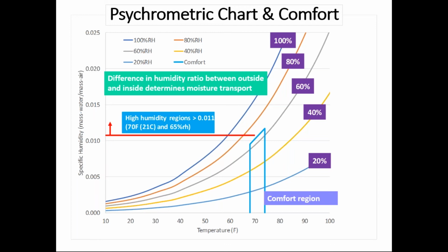Now, marked on this, roughly from about 68 degrees to about 74, 76 degrees is where most people feel comfortable, and over a fairly broad humidity range, up to about 65% relative humidity, which would be 0.01 to 0.011 humidity ratio, basically 1% of the air is water by mass. This would be the region that most people feel comfortable in, but it's very fuzzy. It depends on the time of year, the clothing, your activity level, and personal preference.